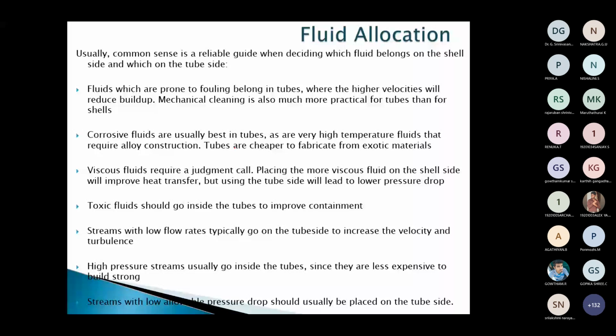Right. Coming to the high pressure streams, as I said earlier, high pressure, high temperature fluids should be placed on the tube side. So this is how we have to select the fluid, whether it is tube side or shell side.